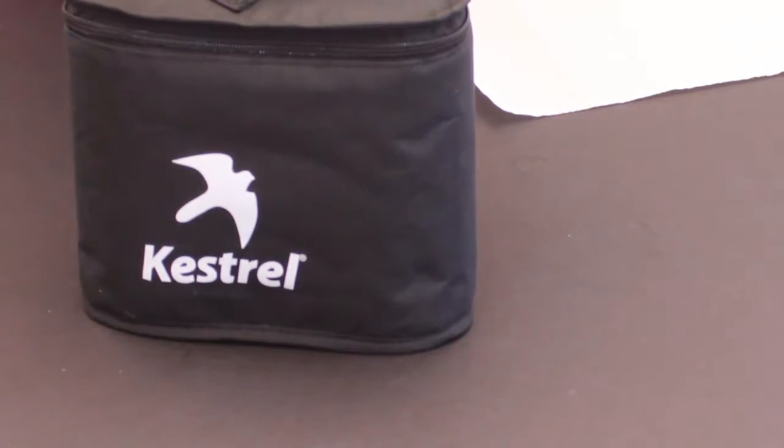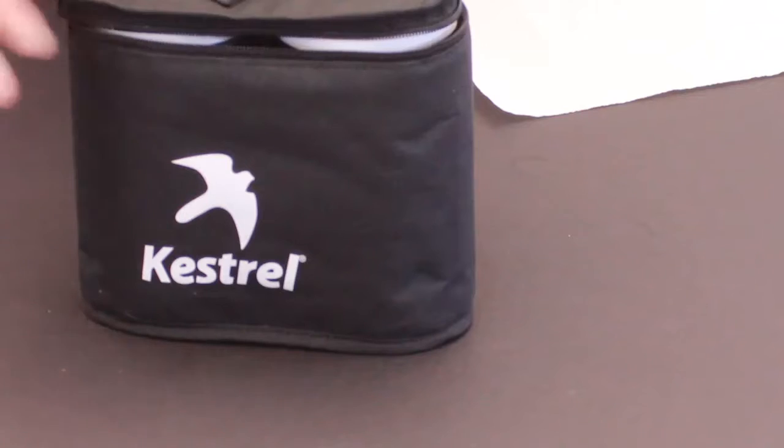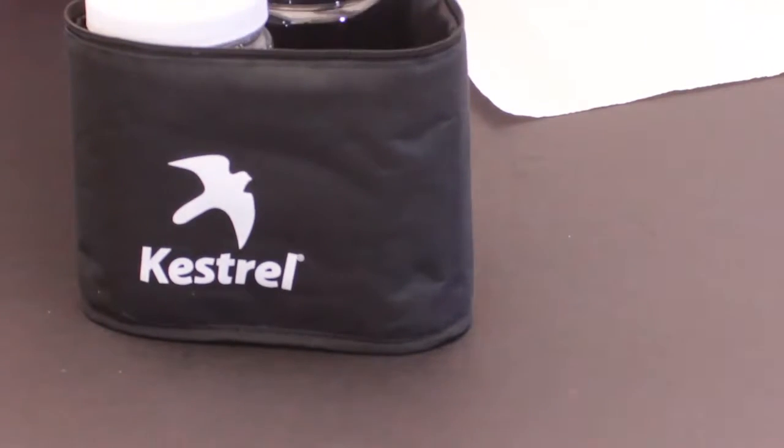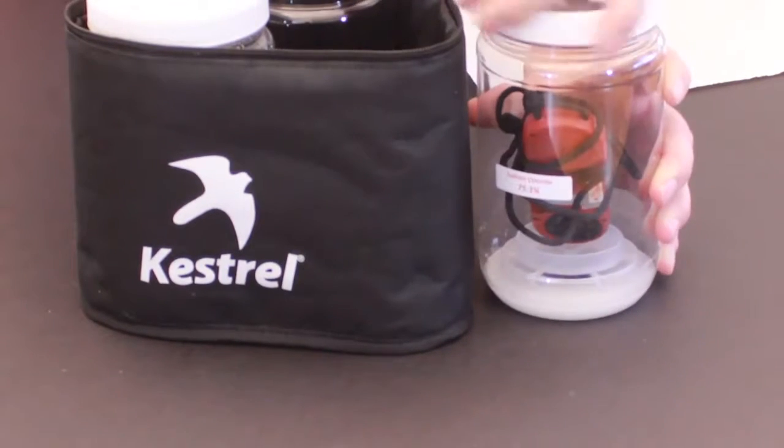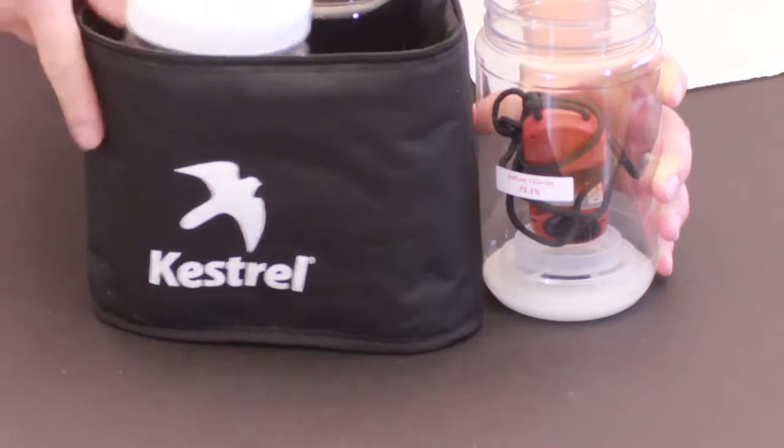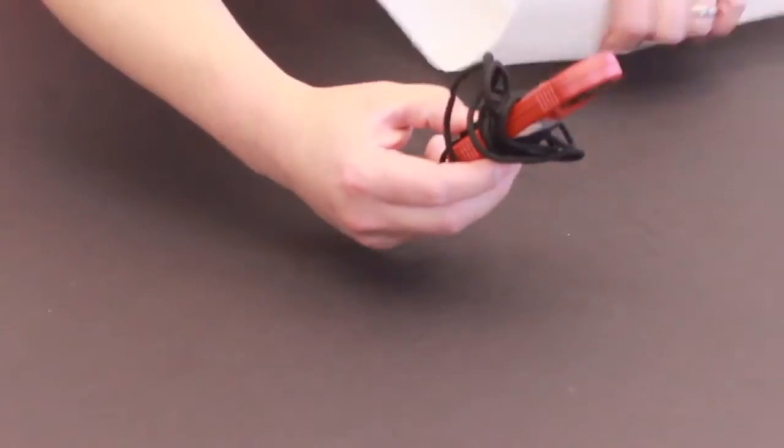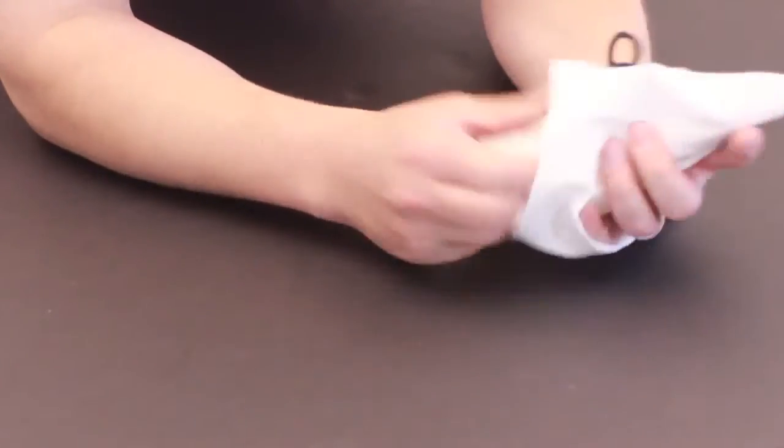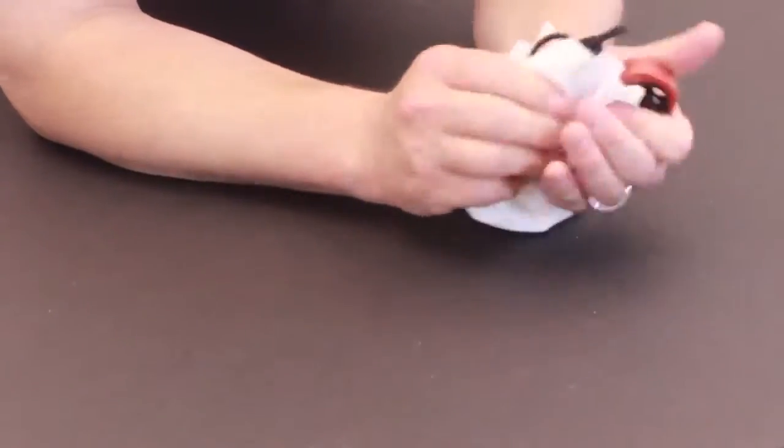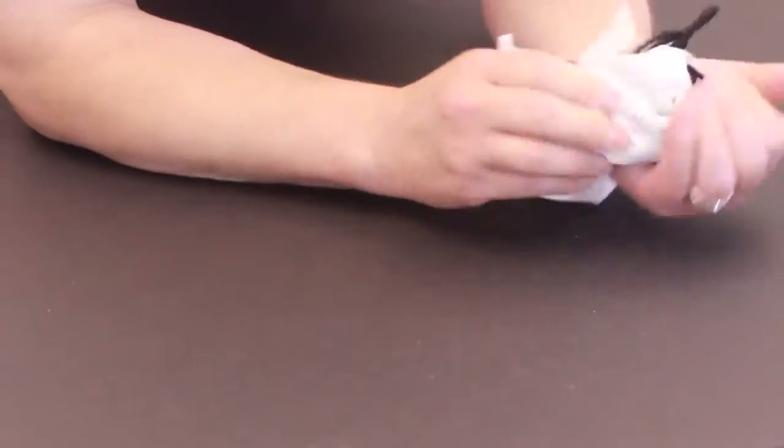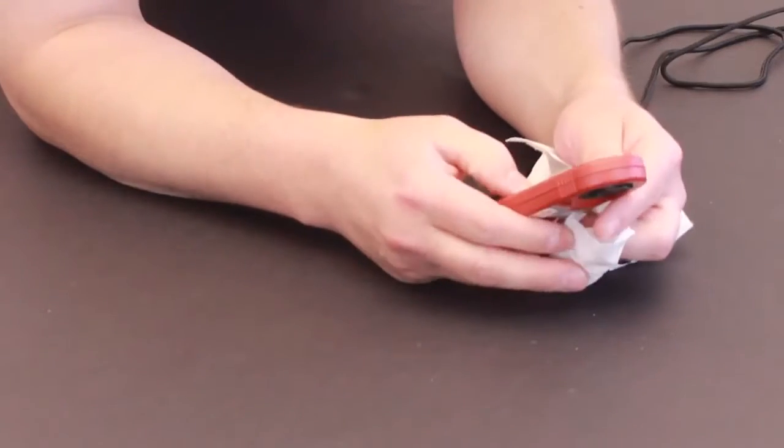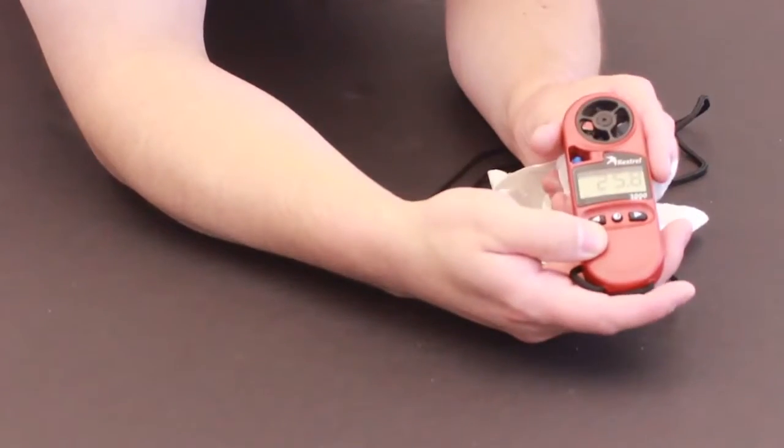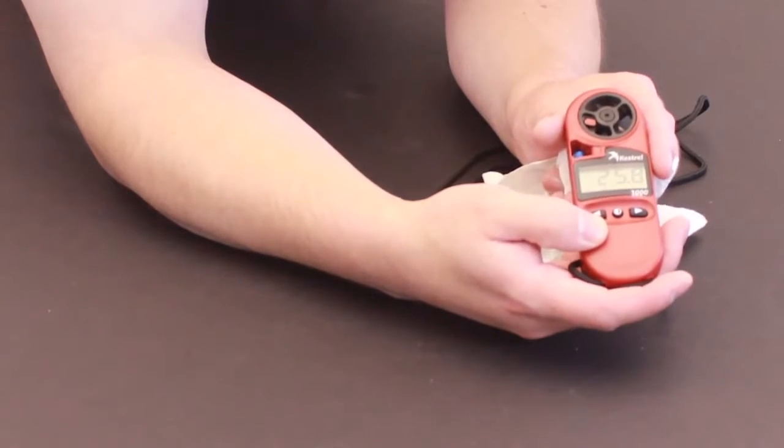Another hour has passed, so let's open up the calibration kit. We're going to open up the sodium chloride chamber. The unit will say end on it, signifying that as complete, but we also want to wipe it off. Make sure any excess salts are not on the lanyard or anything like that. Once we hit the center button, we're back into the regular mode of operation with a calibrated Kestrel.